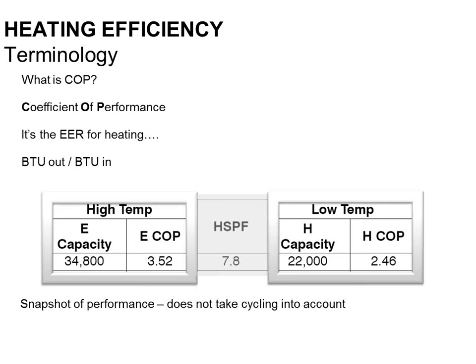That means at the 47 degree number, if you ran him at full load, he's approximately 3.5 COP. That's 350% efficient, right? If I drop it down to 17 degrees outside, he's 240% efficient, a 2.4 COP. That's something that's hard for people to get their head around, is that a heat pump, just like an air conditioner, gives me more cooling and heating capacity than the amount of energy that I buy, right? When I run your air conditioner, it's 350% efficient or whatever it happens to be. For every unit of electricity I buy from the power company, I'm getting 3.5 times that many units of cooling effect. Same thing's happening on this heat pump. For every unit of electricity that I buy from the power company, I'm getting 3.5 units of heat, right?